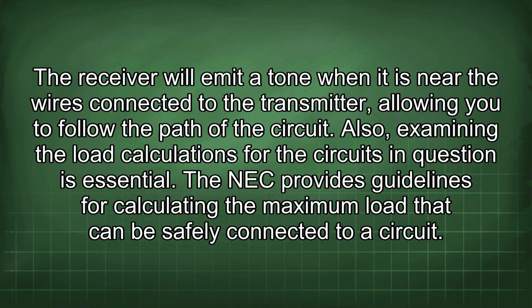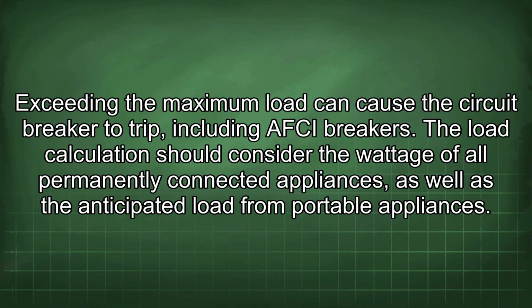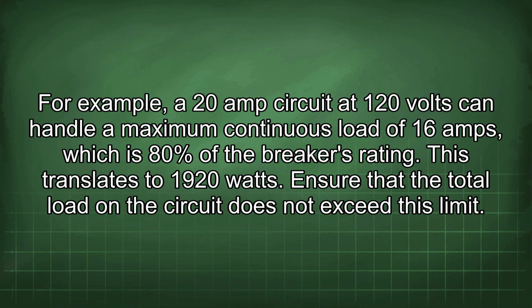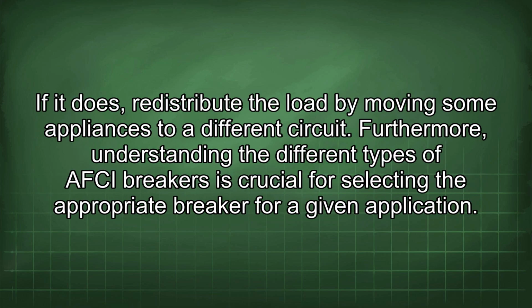Also, examining the load calculations for the circuits in question is essential. The NEC provides guidelines for calculating the maximum load that can be safely connected to a circuit. Exceeding the maximum load can cause the circuit breaker to trip, including AFCI breakers. The load calculation should consider the wattage of all permanently connected appliances, as well as the anticipated load from portable appliances. For example, a 20 amp circuit at 120 volts can handle a maximum continuous load of 16 amps, which is 80% of the breaker's rating. This translates to 1920 watts. Ensure that the total load on the circuit does not exceed this limit. If it does, redistribute the load by moving some appliances to a different circuit.